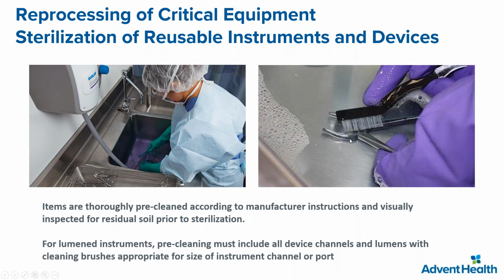And the other picture is showing that if the instrument has hinges, that needs to be open, and they need to use a brush to remove any kind of debris, blood, or any material that was left during surgery. So items are thoroughly pre-cleaned according to the manufacturer instructions and visually inspected for residual soil prior to sterilization. Remember, sterilization has its capability, but if the instrument is dirty, it's not going to be sterilized. It cannot be considered sterilized. For instruments that have lumens, little passages, pre-cleaning must include all device channels and lumens with cleaning brushes appropriate for the size of the instrument, channel, or port.